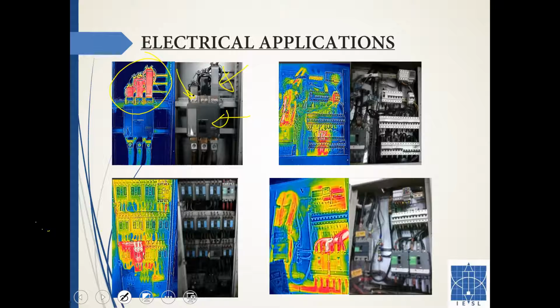If your breaker is under a similar load, so in this phase you have a similar load, and if you have a hotspot here and here, there are ways to evaluate that connection - whether it's too hot or not, and how hot is too hot. You need to bear in mind you're comparing two different components here.